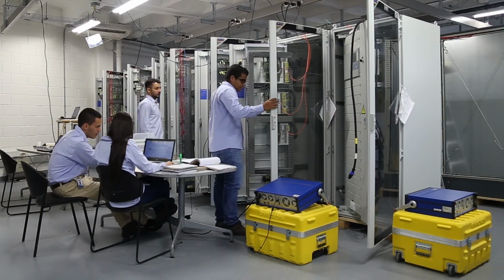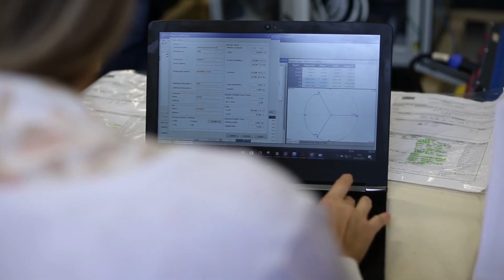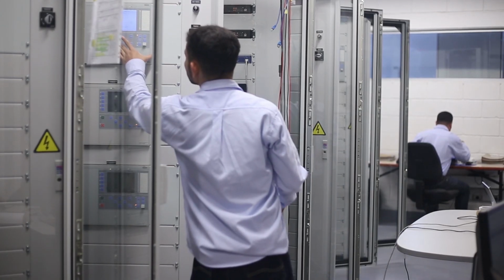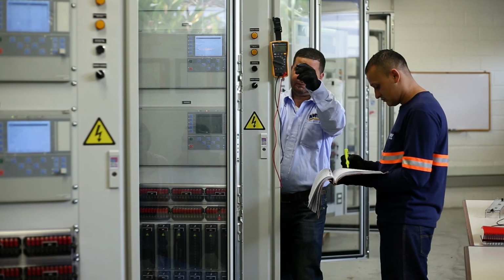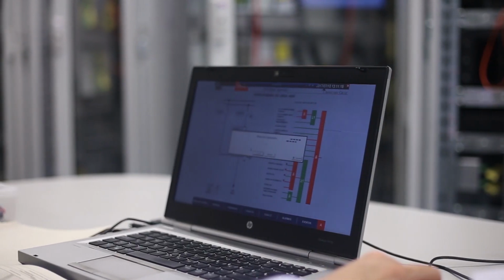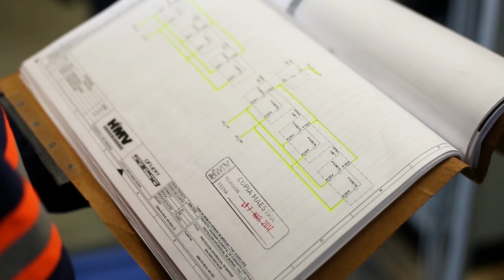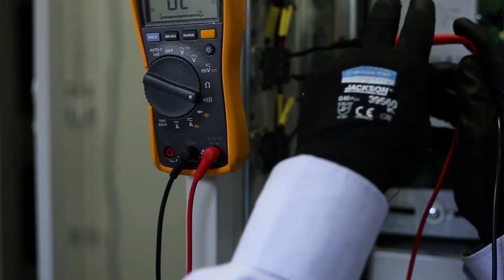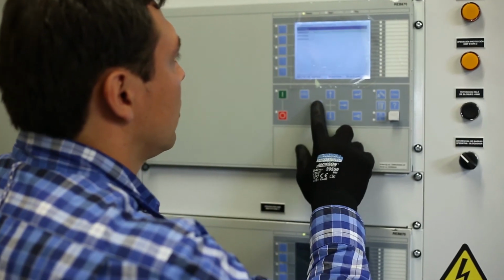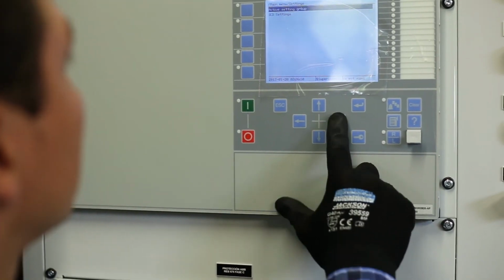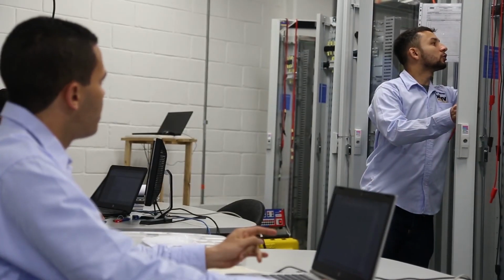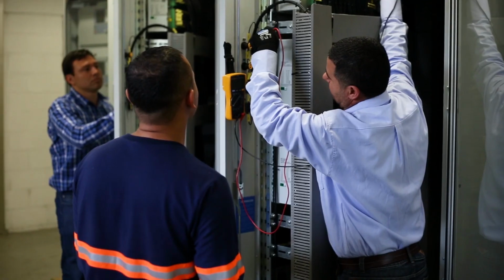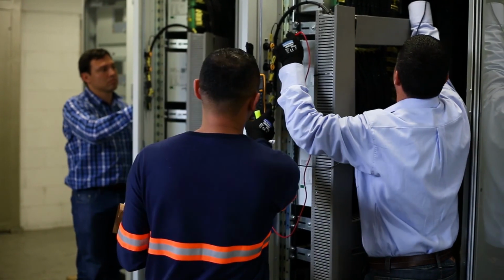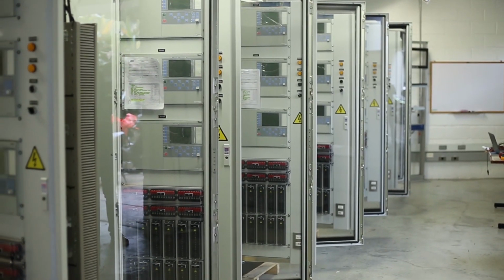Finally, the cubicle passes to the testing area for the factory acceptance tests, where the following verifications are performed: point-to-point wiring check, mechanical assembly and equipment arrangement verification, full factory testing, including protection relays and controllers programming and settings, and in general the cubicle overall function verification. The control and protection systems are programmed and fully factory tested, minimizing site commissioning time.